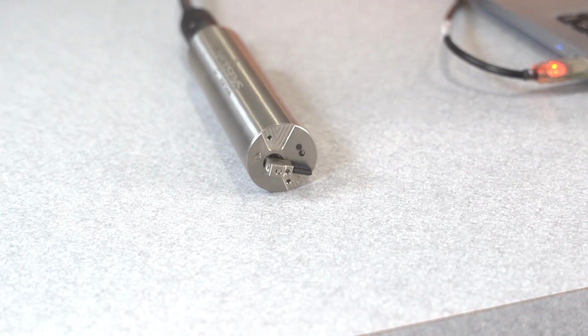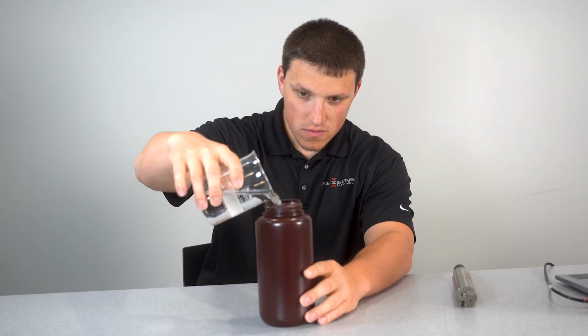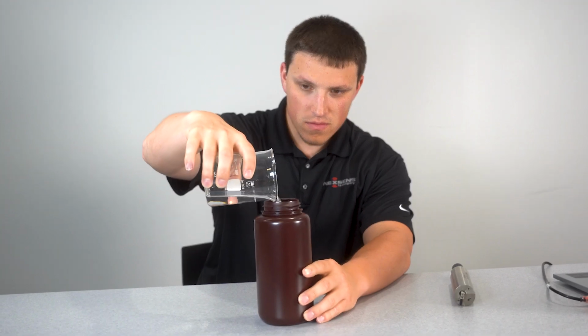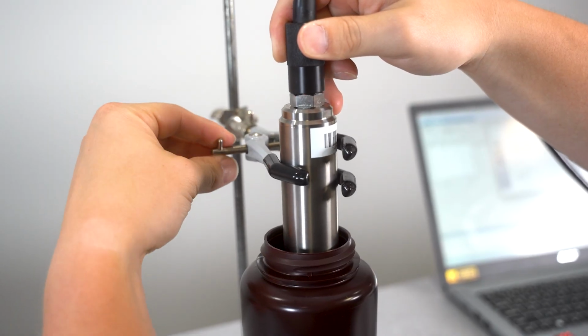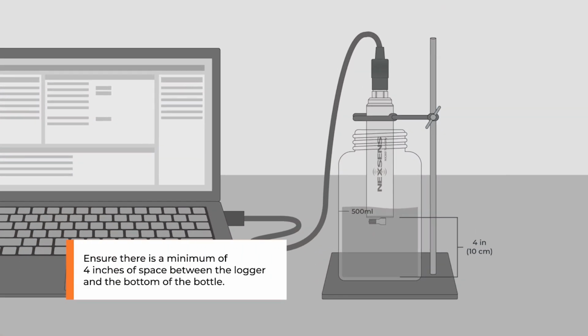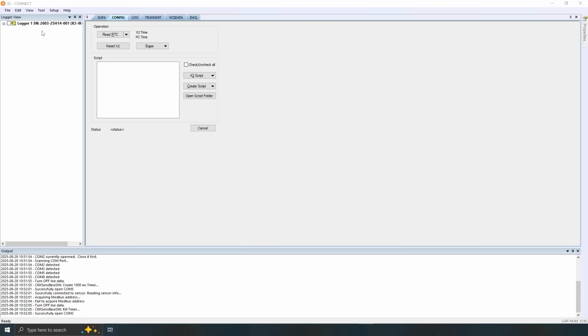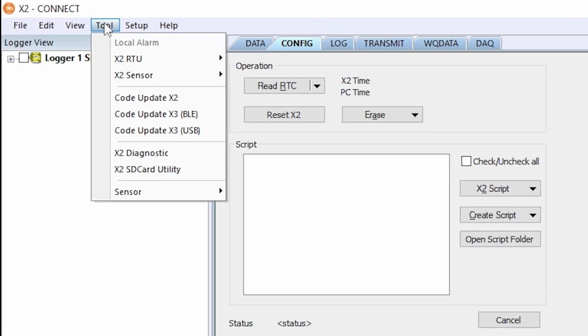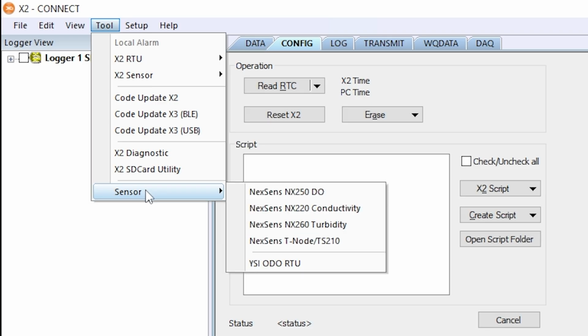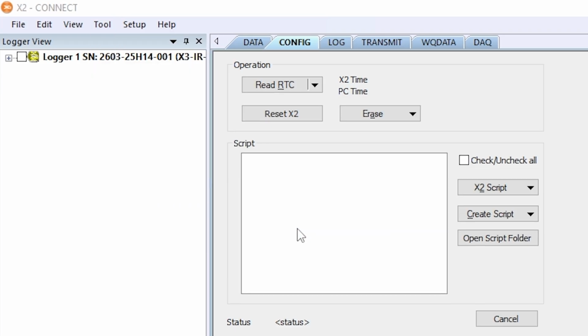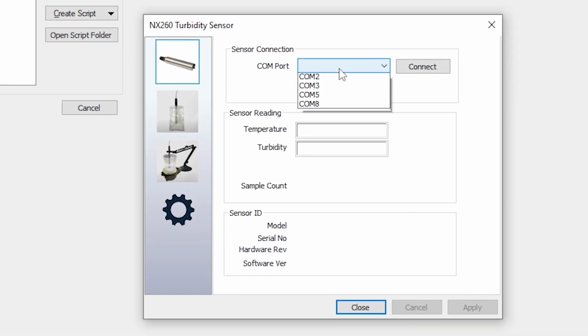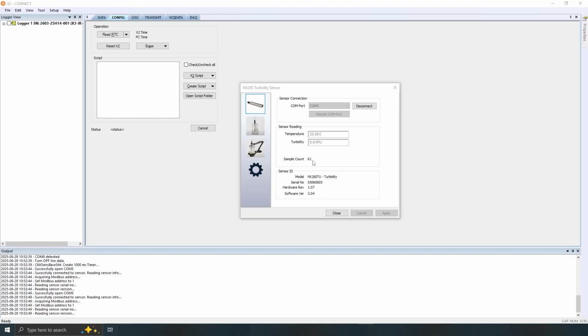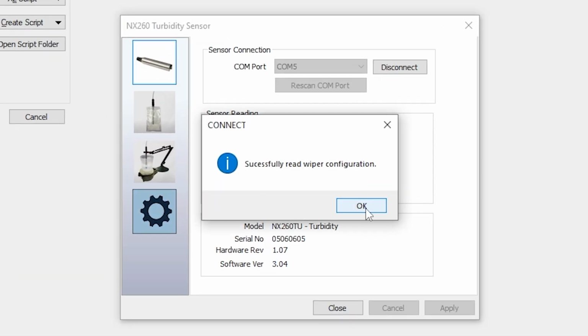To prepare for measurements, fill an amber bottle halfway with tap water. Clamp the sensor and center it to minimize ambient and reflected light. Now it's time to test the connection. Open Connect and go to Tool, then Sensor, and select the NX260. Select the previously noted COM port and readings will begin to update. Click the gear icon to ensure the wiper works.